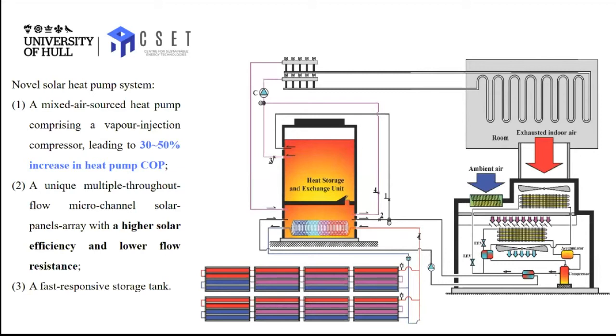And the third part of technology is a fast responsive heat storage and heat exchanger. If you look at this diagram, we got a tank. We have a tank separated into two parts. At the low part of the tank, we got a very, very small volume space, maybe 20 liters or 30 liters. With this space, we got a heat exchanger embedded that allows heat transfer between solar loop fluid and heating loop fluid. Because of the small volume, this amount of fluid could be quickly heated in about 20 minutes.